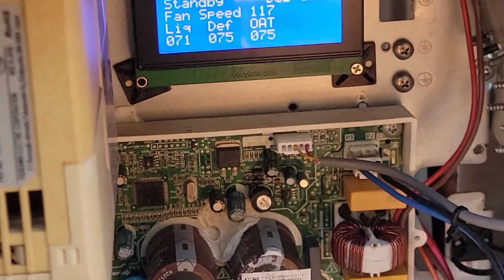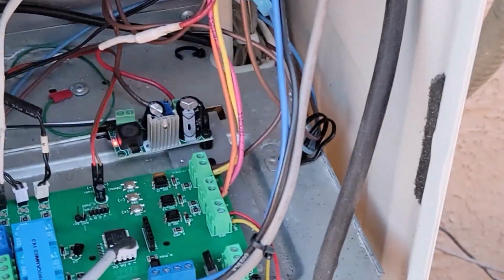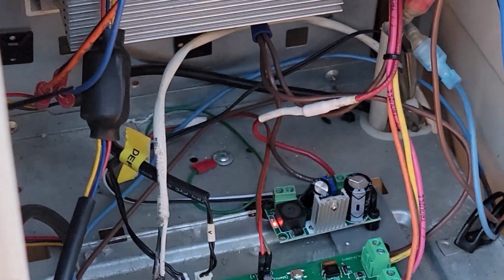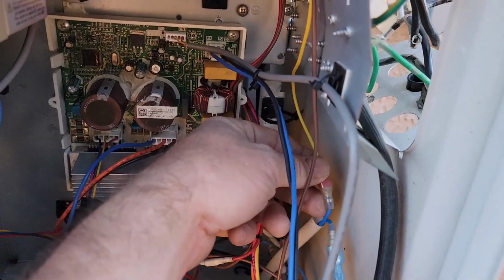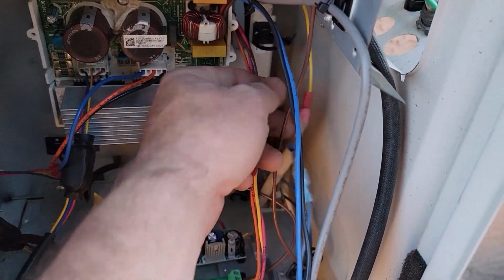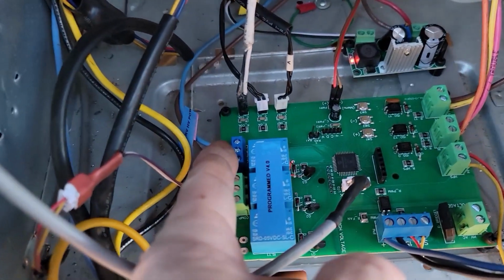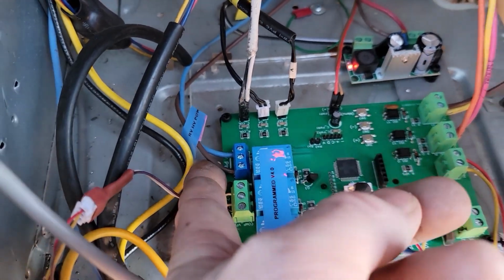So that's cool, I need to put the high voltage on now. I'm always paranoid when it comes to high voltage. So, high voltage comes down - this is the reversing valve. One leg goes that way, one leg goes through the reversing valve relay, which is right here.